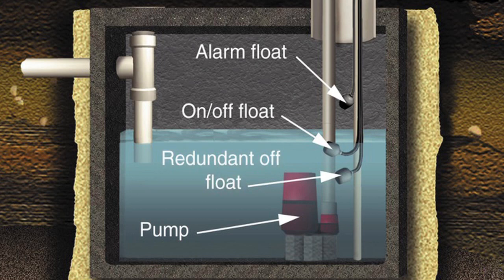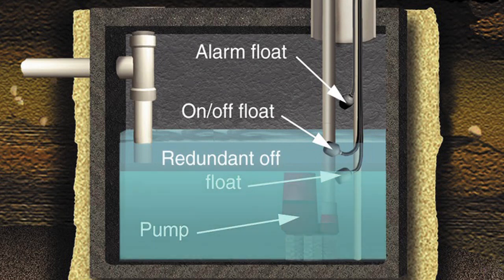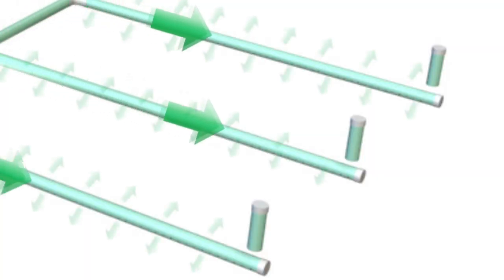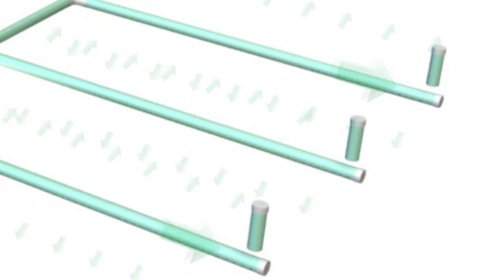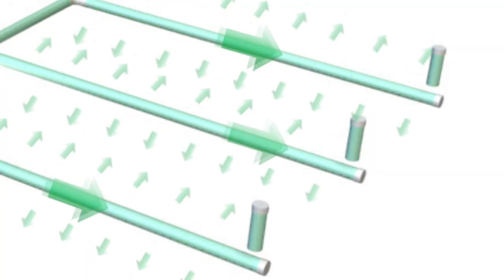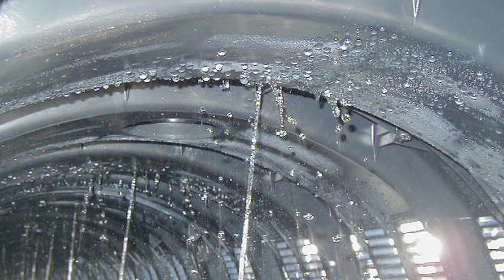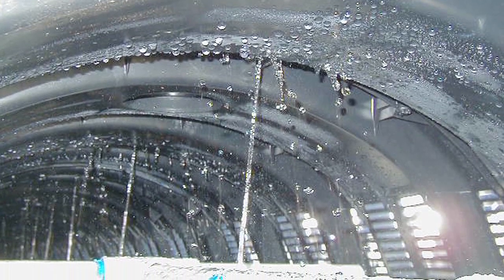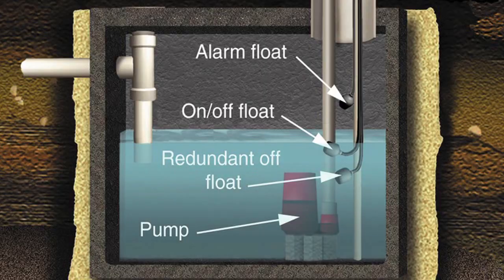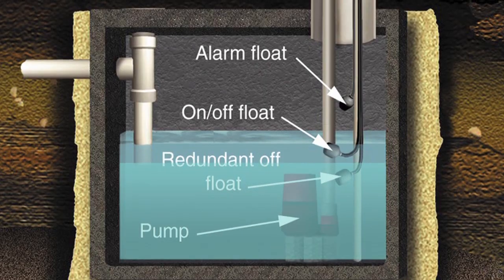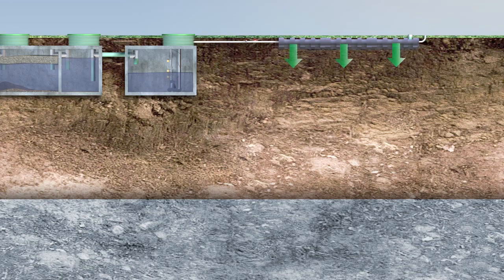The redundant off float prevents the pump from turning on if there's not adequate wastewater to cover the pump. The on/off float turns the pump on as the wastewater level rises. The effluent is dosed every few hours and is spread out across the whole bottom of the trench. Some pumps operate on demand while others use a timer to start a pump cycle. As the pump moves wastewater into the drain field, the level drops, dropping the float and turning off the pump, providing the soil with time to dry out between doses.